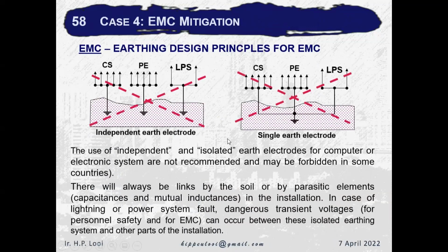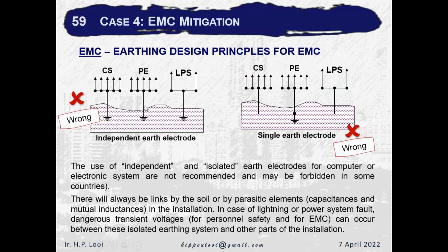Okay. Another case is in a building. Commonly, people do it like that or like that. These are not allowed, because if you do that, there may exist within the building a potential difference between the common earth, the LPS, and the protective earth. Protective earth is actually the electrical earth. CS might be the communication earth. So you cannot do this. This is definitely not good.